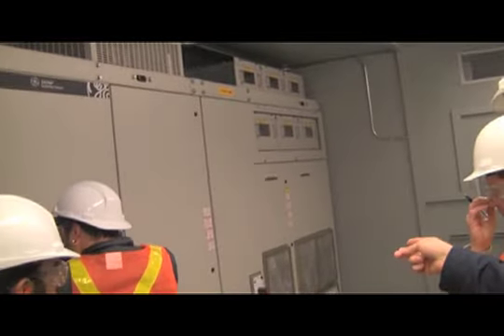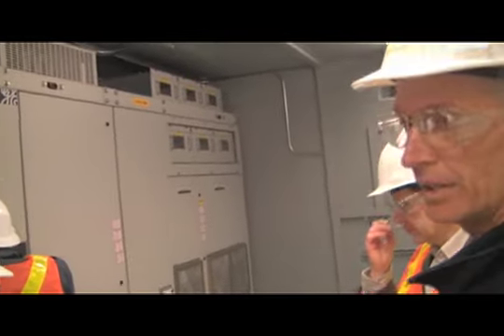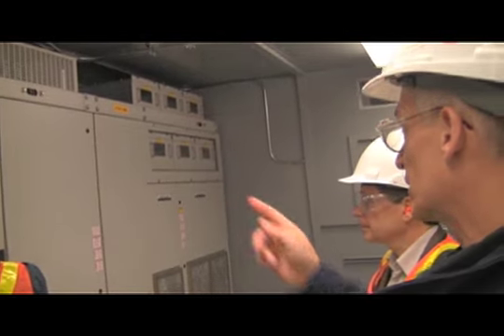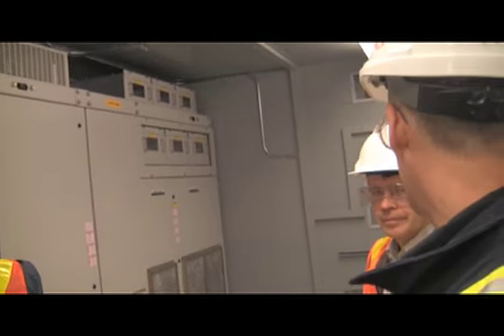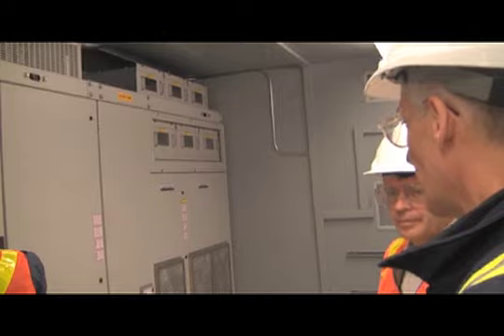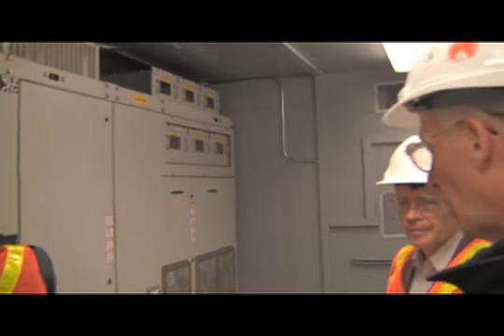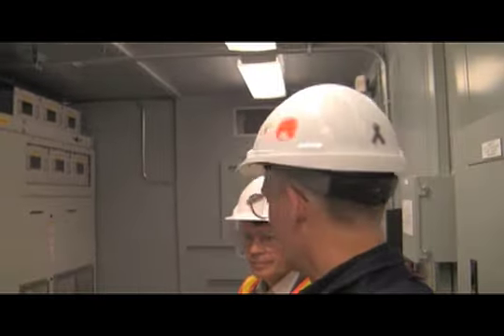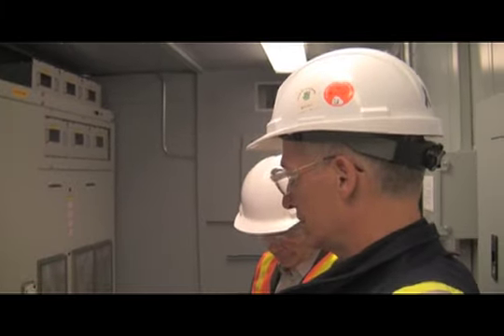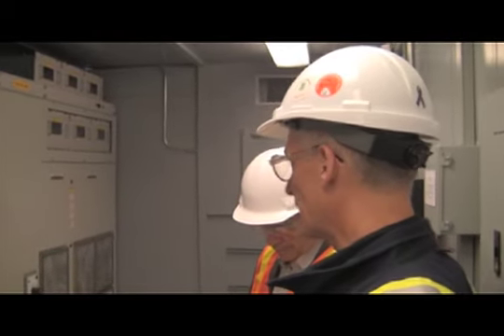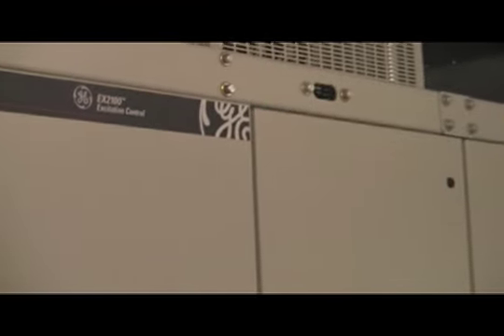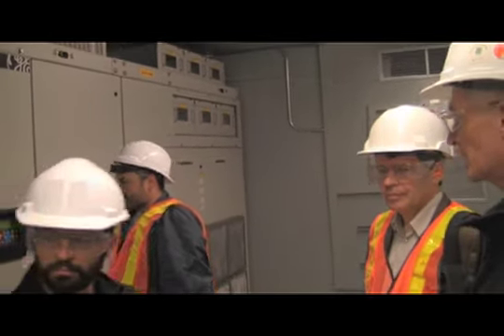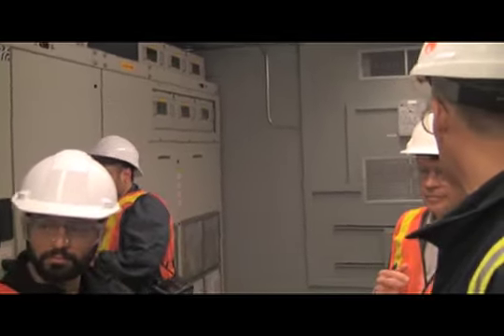We've got a large switchgear here, and that's the excitation system. Basically what you want to do with the generators, it's just a huge coil rotating in a magnet, and the bigger the magnet, the more power you can generate. So we want to make the magnet as big as possible for the size, and that's how we facilitate it here. And then the switchgear behind us, what that does is allow us to start the machine up.